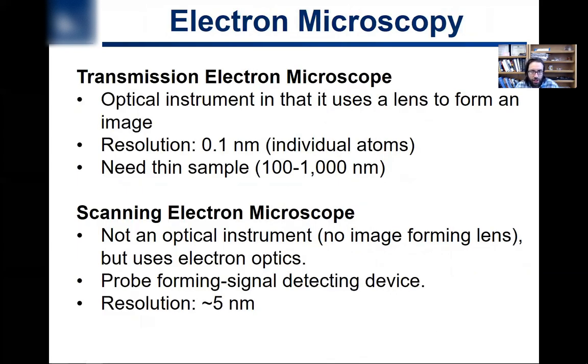So transmission electron microscope versus scanning electron microscope, which we'll talk about in a bit. It's an optical instrument in the sense that it uses lenses—it uses electromagnetic lenses to form an image. As you'll see, SEM is not an optical image. We don't use any lenses, but we use electron optics to direct the beam. And you're basically scanning the beam back and forth, rastering it, kind of similar in some sense like an AFM or an STM.